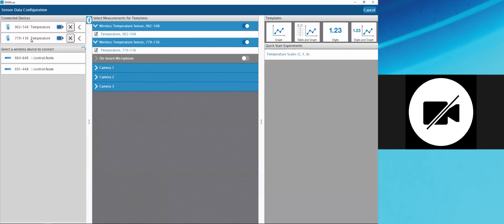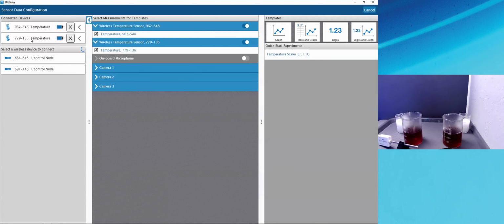Yes, actually, we had a question about how many sensors you can connect. I know we can connect up to 4. Some I've seen up to 6, depending on the software used. But we also have sensors that have several sensors built within them, like our weather sensor that can take up to 19 measurements.